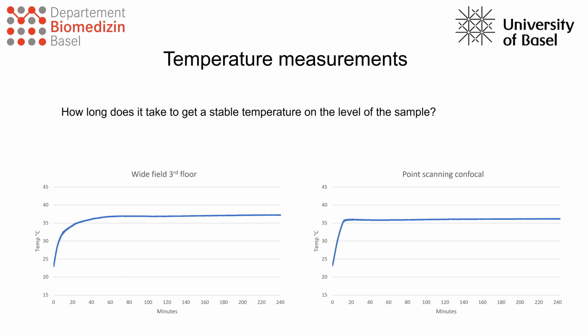So as I said, first of all, we looked at how long it takes, when you switch on these heating units, to get the whole box onto a stable temperature. And we could see that in some cases the plateau is reached faster than on other devices, but roughly it takes around 60 minutes to get a stable temperature. So we measured several of our microscopes, and these are just two plots that I show here.